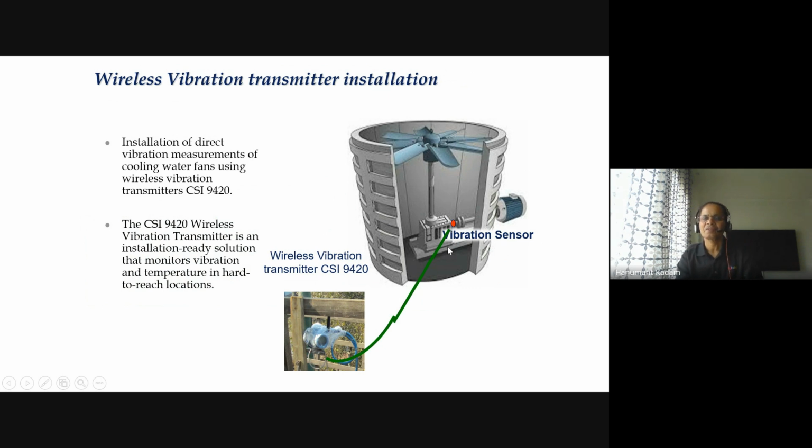So this vibrates. So vibration sensors are there on this and the motor also. And the only difficulty was there. It is not properly maintained, and we were not getting a reading status of the fan, and that results in, we can say, accidents.